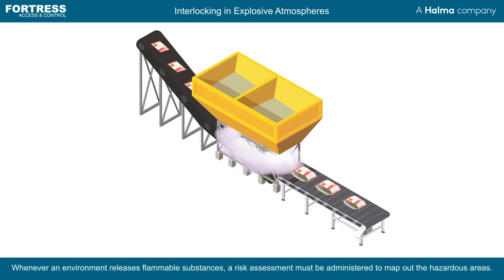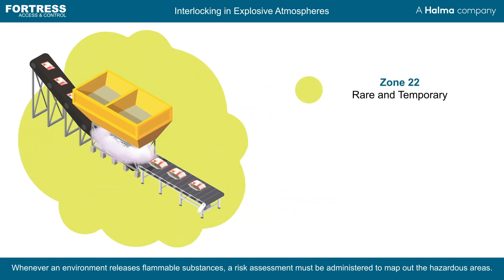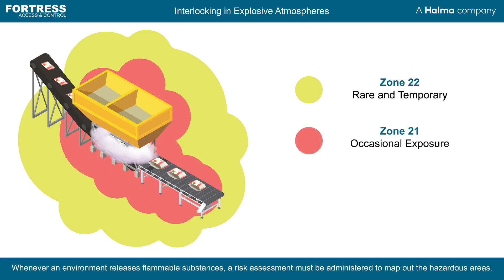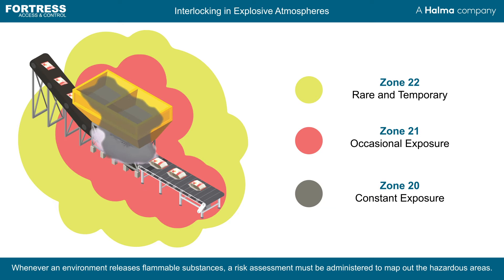The space surrounding the process creating these ignitable substances can be assigned into three zones. Zone 2/22 is an area where an explosive atmosphere would only occur very rarely and not in normal operation. Zone 1/21 is an area where an explosive atmosphere is likely to occur occasionally in normal operation. Zone 0/20 is where you would find a constant explosive atmosphere, typically found within the machine. Outside of these areas, ignition will not cause an explosion. A risk assessment would typically be used to identify these zones to guide installers and integrators to where electronic equipment can be located.